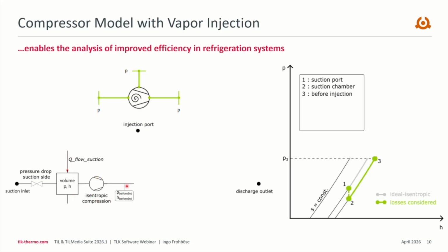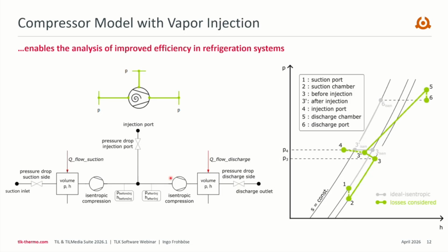So then we are here at the point 3 before the injection, and the pressure at the outside of the injection port is a little bit higher than inside. So therefore the flow goes into the compressor at the injection port, and we have another, second stage of isentropic compression, a high pressure volume, and a discharge pressure drop. So we are ending here at position 6.